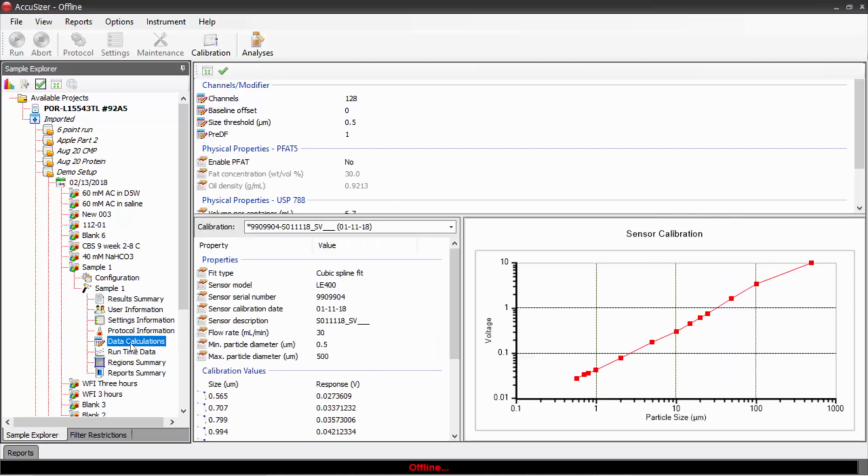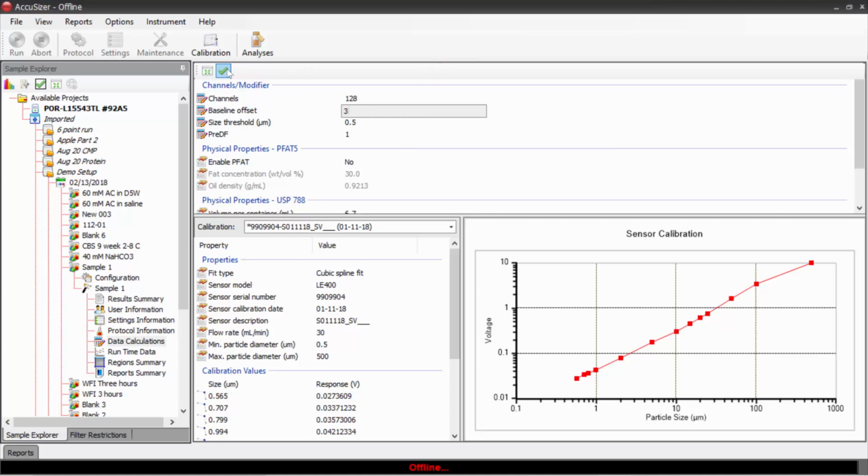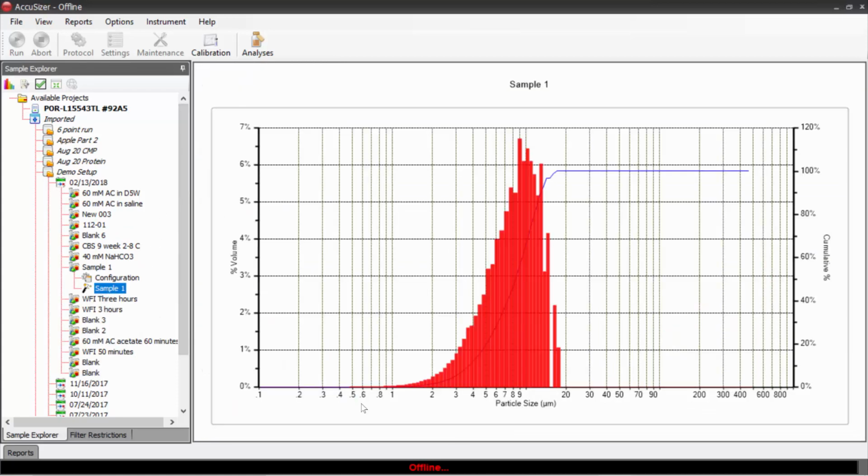I could come back into Data Calculations and see baseline offset. If I enter the number 3 here, for instance, now any histogram band that has fewer than 3 counts will not be plotted. I click green yes, and if I look at sample 1 now I have a much better view of the volume distribution.